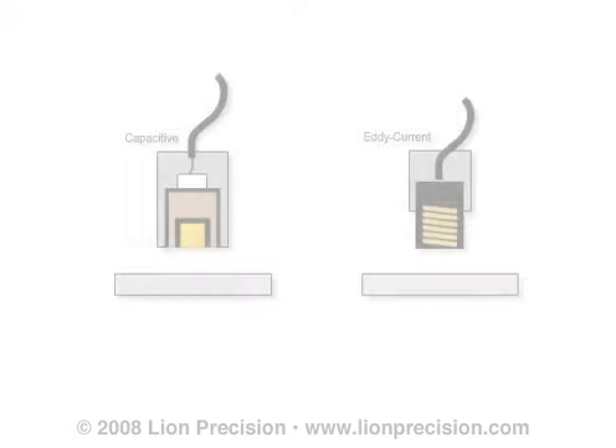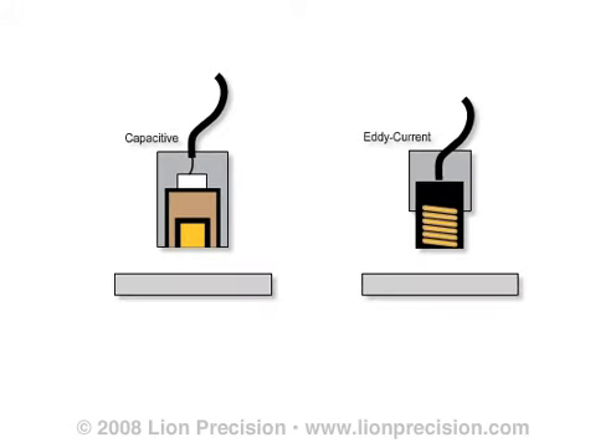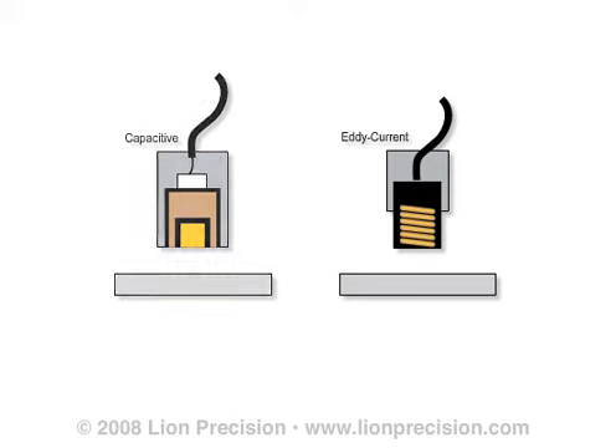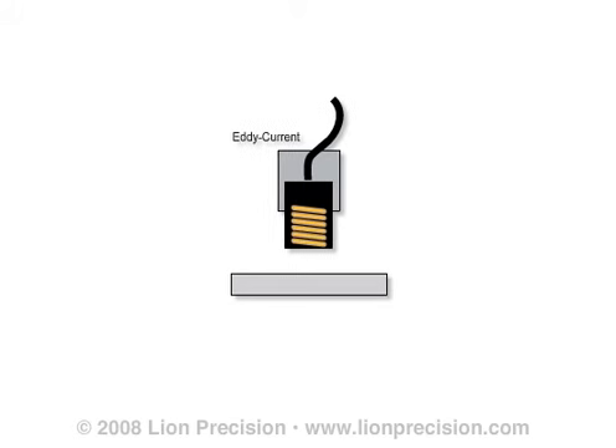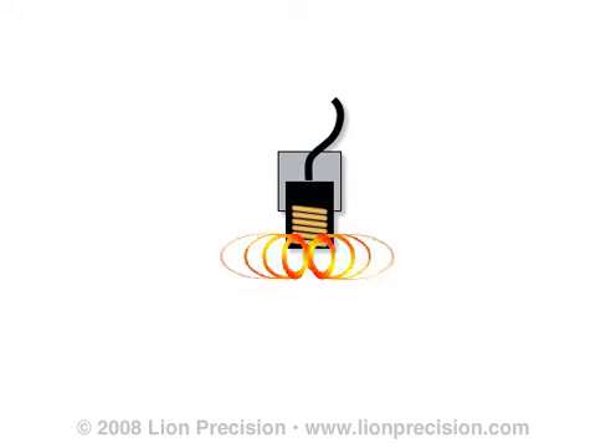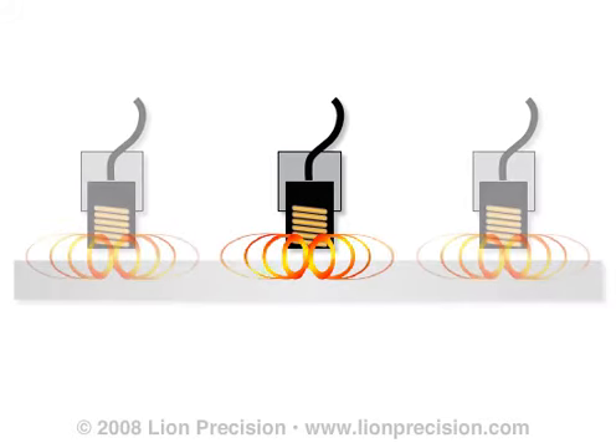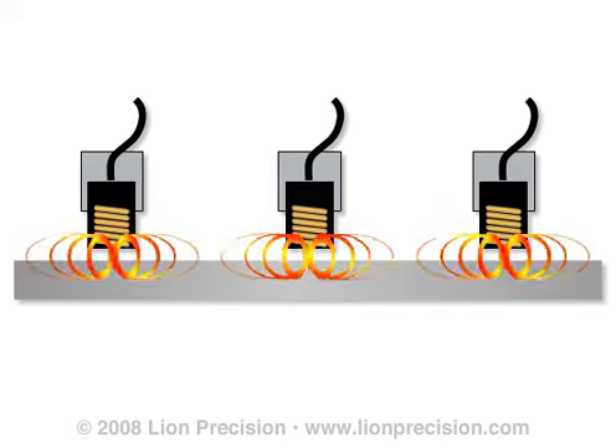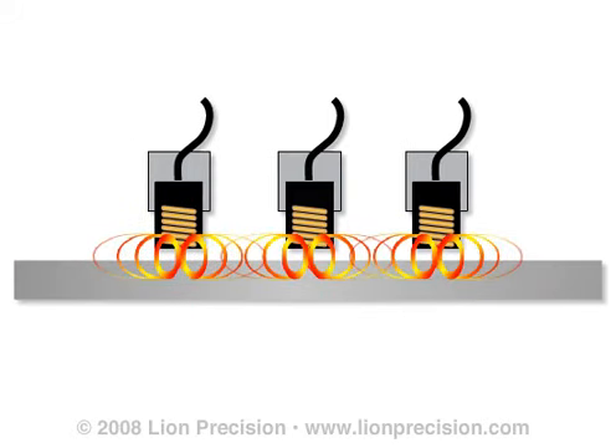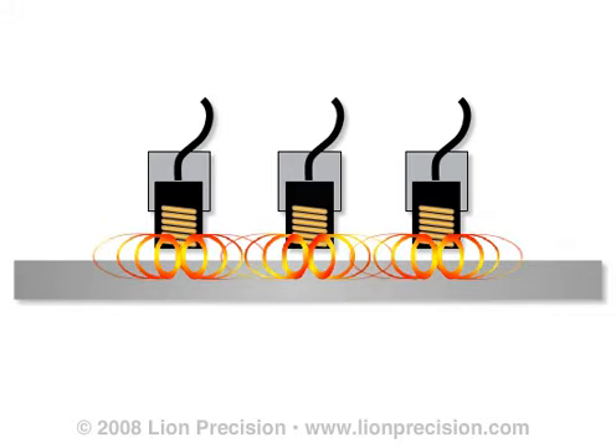Because of differences in the shape and reactive nature of the sensing fields of capacitive and eddy current sensors, the technologies have different probe mounting requirements. Eddy current probes produce comparatively large magnetic fields. The field diameter is at least 3 times larger than the probe diameter and greater than 3 diameters for large probes. If multiple probes are mounted close together, the magnetic fields will interact. This interaction will create errors in the sensor outputs.